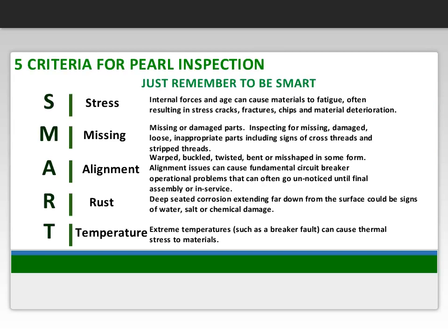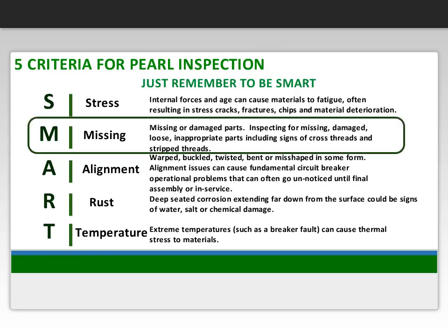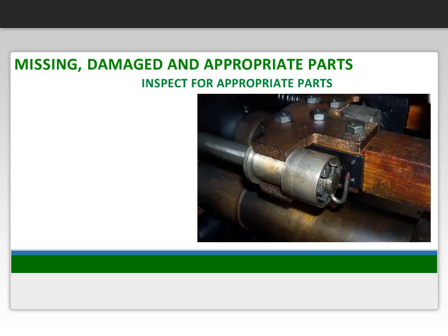The second Pearl inspection criteria is M for missing parts. You'll find this frequently repeated in the standard. It is important to inspect for damaged, loose, missing, and inappropriate parts. This technique found in this particular phrase is used about 14 times in just one standard for power circuit breakers. Now let's examine some examples. Take a look at this photo. Let's pause for a moment to see if you can determine the issue.